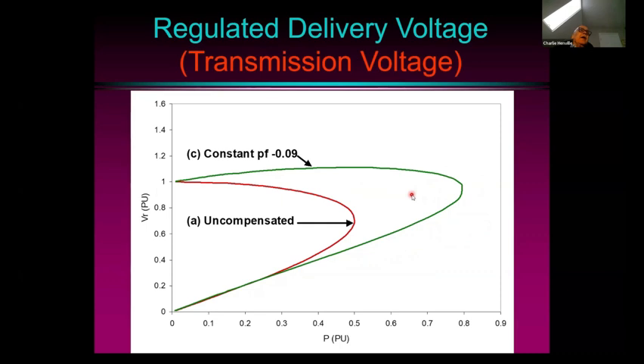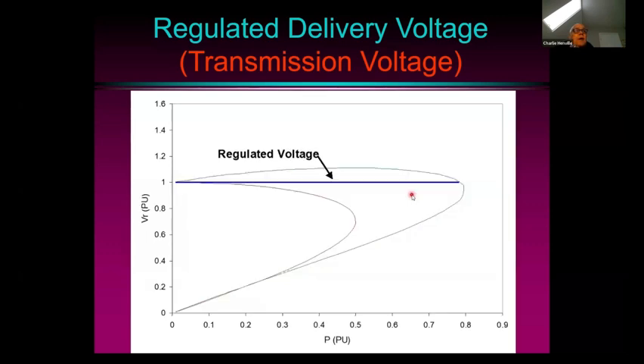So here we have the constant power factor curve again, compared to the uncompensated curve. And this is the type of voltage that we would like to deliver power at. I show 1 per unit. I know many utilities will deliver power at a slightly different voltage, usually a little bit higher, but just for convenience, I show 1 per unit here.